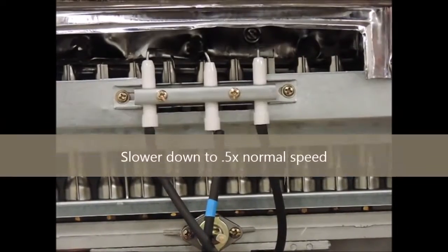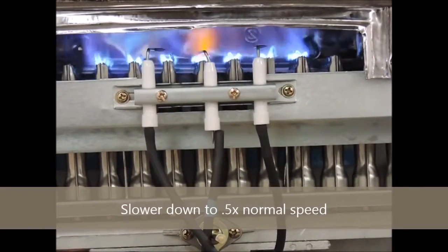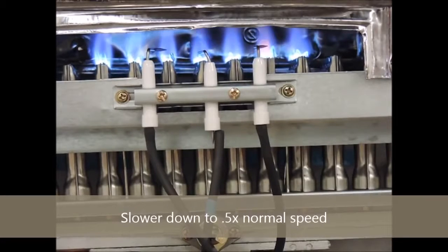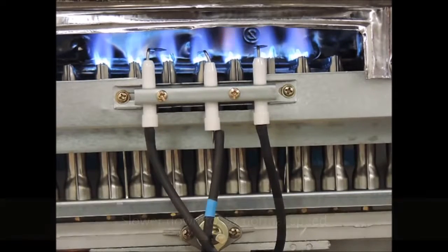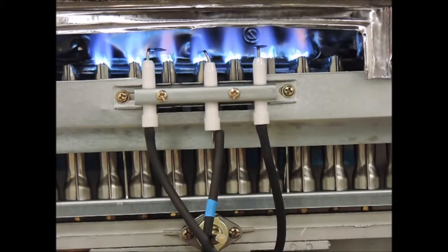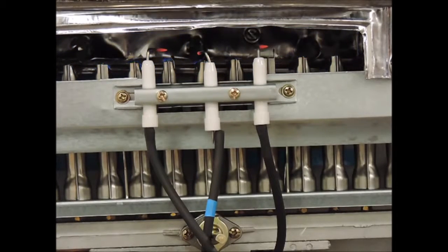If your unit clicks and lights but goes out within approximately 15 seconds, then the first thing you'll want to check is the wire that connects the thermocouple sensor. This sensor is the longer sensor that protrudes over the burner assembly and should have a thick black wire with a blue piece of tape on it. Please make sure that this wire is connected securely.